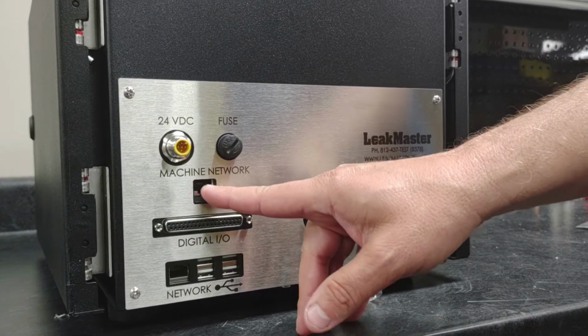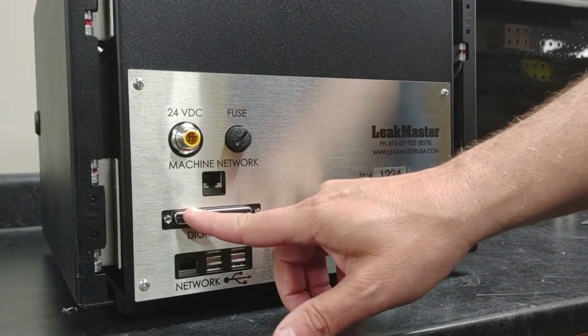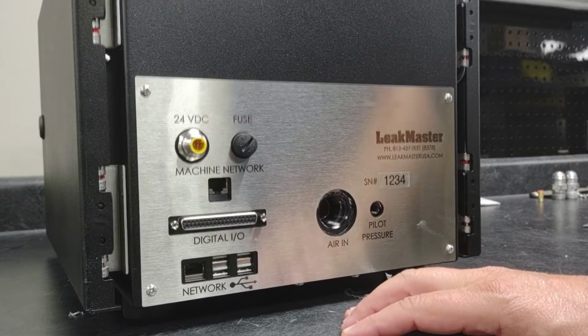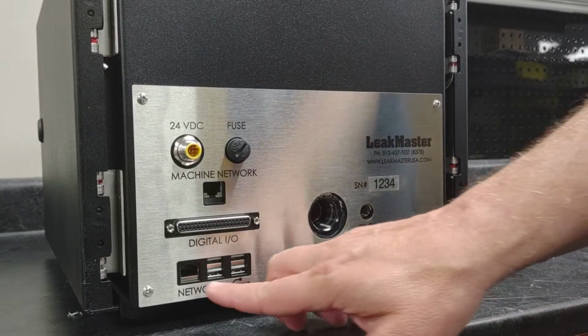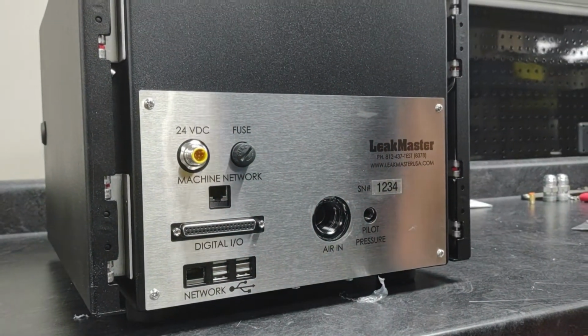Ethernet IP or Profinet is going to be tied to this port. Discrete I/O, if you're using discrete I/O for communications to your PLC. And network, if you want this connected to the internet for update purposes and troubleshooting.